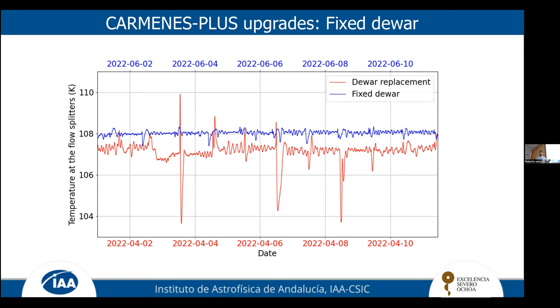Every night, what we do is some calibrations to see how the instrument is performing, radial velocity calibrations. The first one we set to zero, so the rest of the calibrations done during the night are referred to this first one, okay? We do this every night: the first one is zero and the rest are referred to it. We call this drift, which is all the radial velocity calibration measurements taken together.